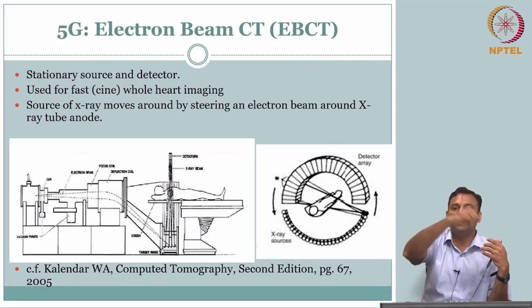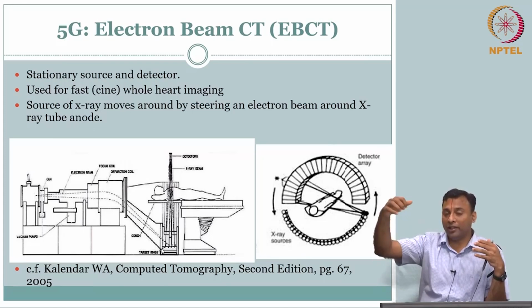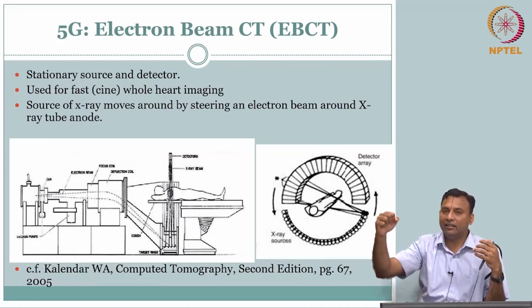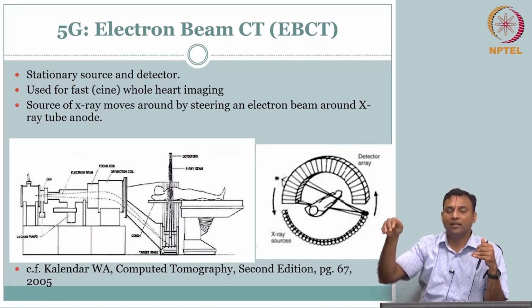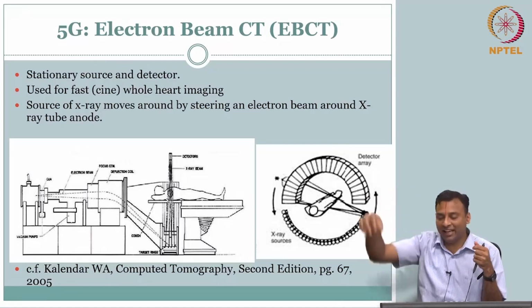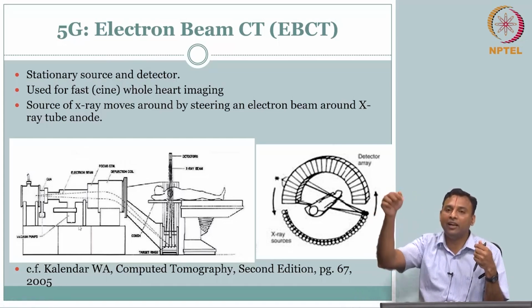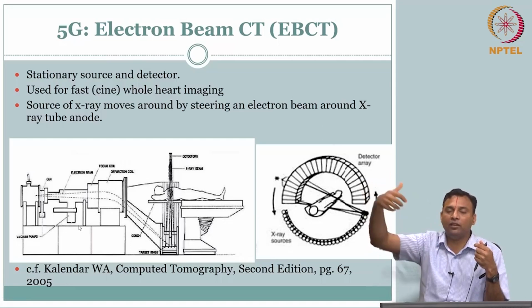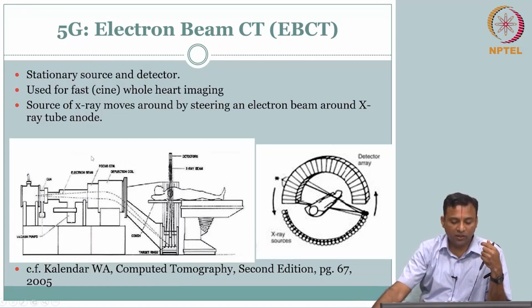Instead of just moving the thing, you say, oh, don't do that. The X-ray tube manufacturing ecosystem is set. We have vendors, so don't do that. Now you say, okay, instead of doing that, can I just have fixed anode plates at different locations, right? The patient will not know anything. Behind, I will essentially have a big setup where I will have my electrons move around and hit a particular anode where I want the X-ray view, right? So that is what this one is.